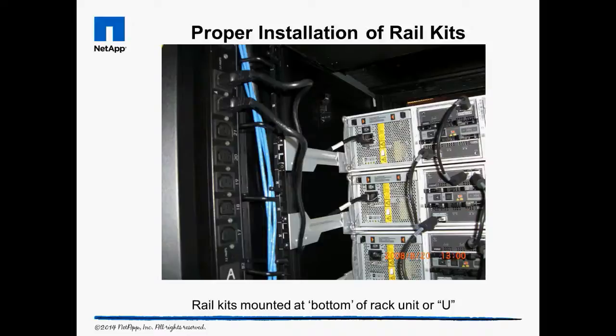A rack unit, or U, is three mounting holes high. In this photo, each rack unit is the three holes between the horizontal lines. The number is next to the middle hole. And a common mistake made by new field engineers is to install rail kits at the number instead of the bottom hole.